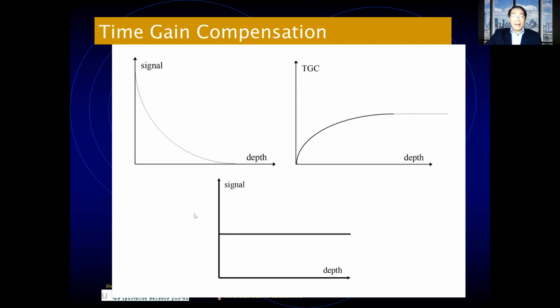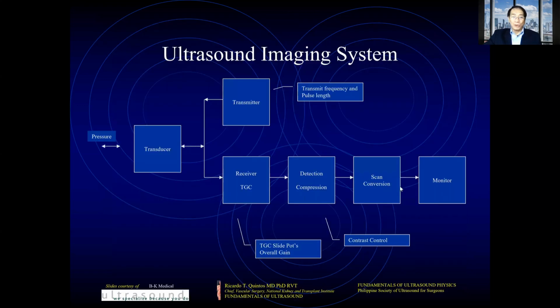by the CPU. And so if you do not have this time gain compensation, you will see that closest to the probe, it's very, very clear, very, very visible, but farthest from the probe, it's going to be very dark and maybe the resolution is not going to be very good. But with the time gain compensation, you can adjust certain switches and knobs in the ultrasound so that the weaker signals will be strengthened, will be picked up more, and become equal to the signals obtained from the echoes closer to the ultrasound probe. And then you will have a more homogeneous image. So more of this in the lecture on knobology following this module.